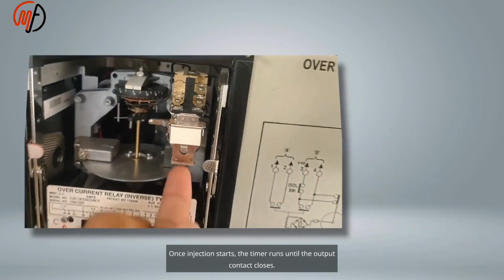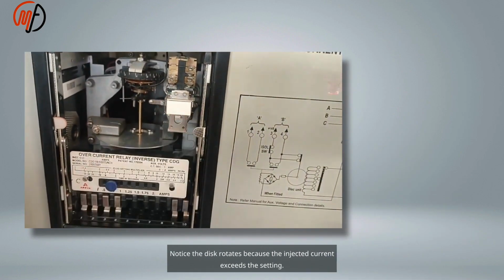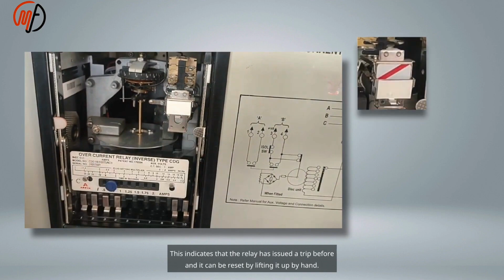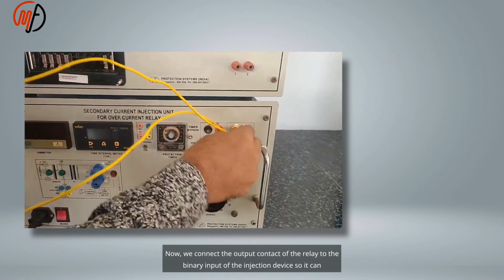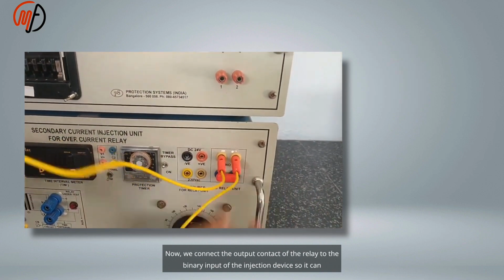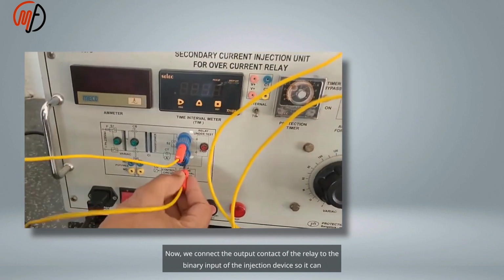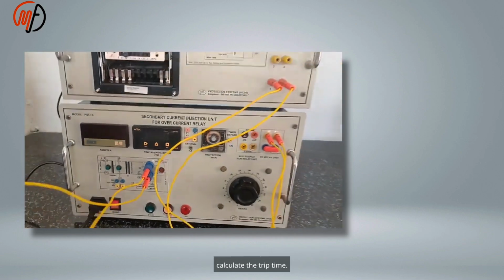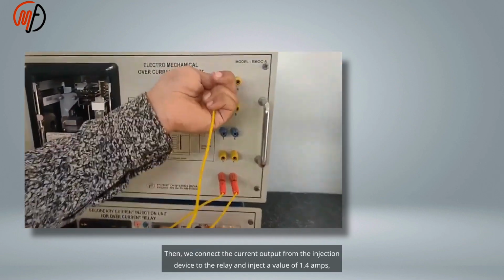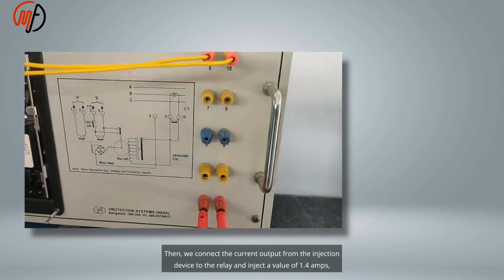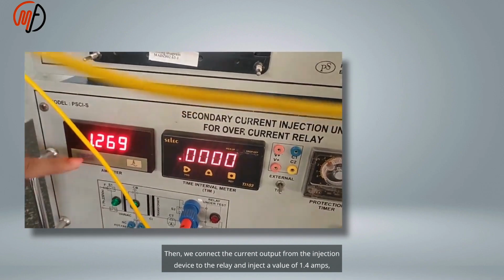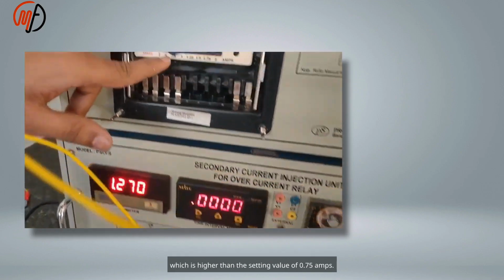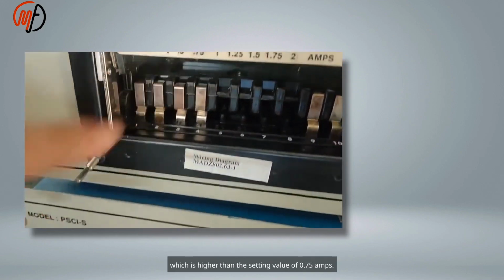Once injection starts, the timer runs until the output contact closes. Notice the disk rotates because the injected current exceeds the setting. This indicates that the relay has issued a trip before, and it can be reset by lifting it up by hand. Now, we connect the output contact of the relay to the binary input of the injection device so it can calculate the trip time. Then, we connect the current output from the injection device to the relay and inject a value of 1.4 amps, which is higher than the setting value of 0.75 amps.